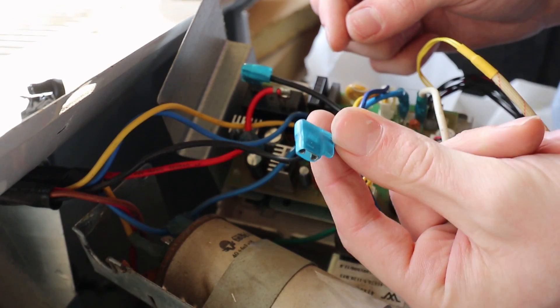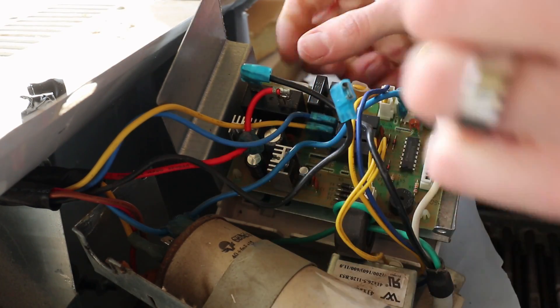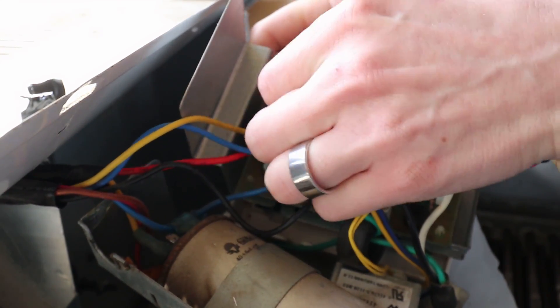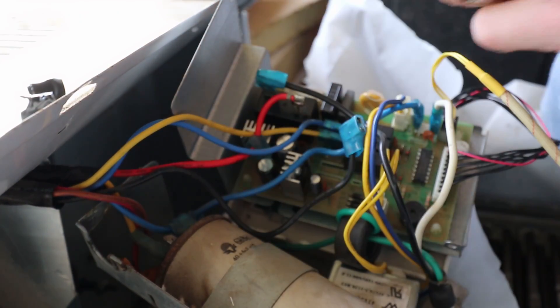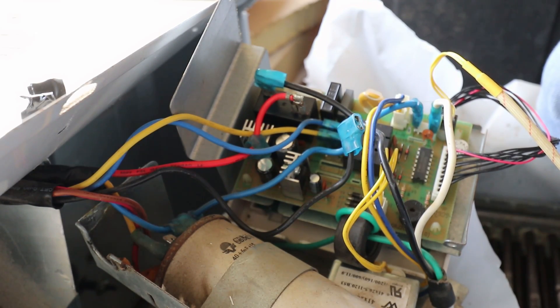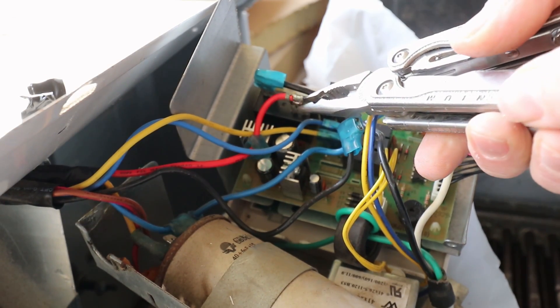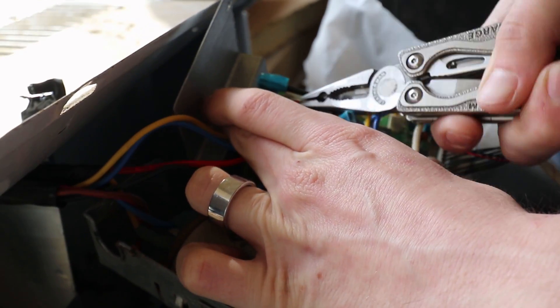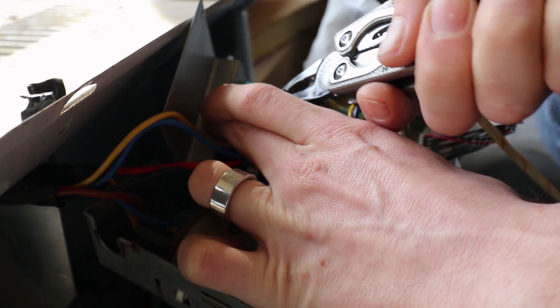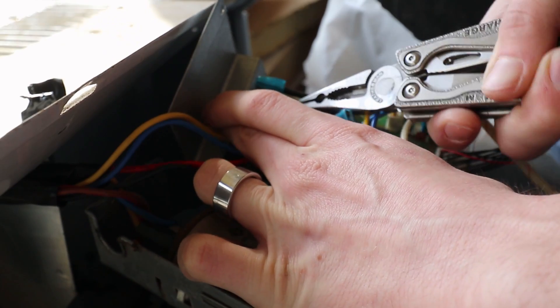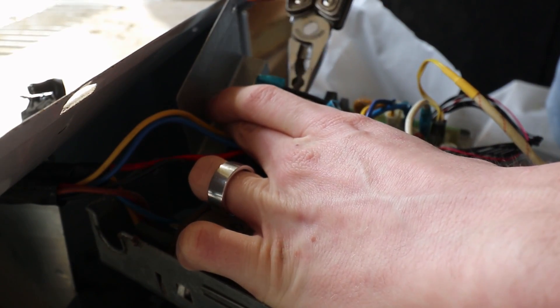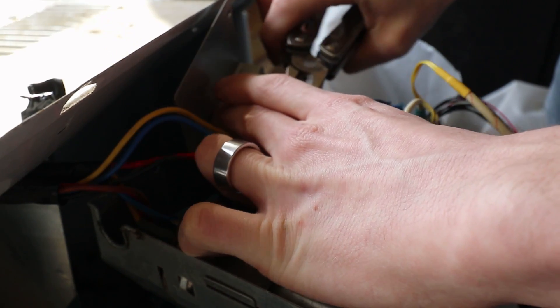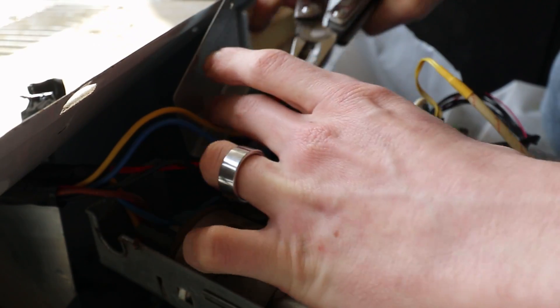So we've got what needs to be hot for our fan. We've got here what needs to be hot for our compressor. Keep in mind too that these capacitors can hold charge by design. They hold charge even when everything's unplugged, so be careful when you're in here messing around that you don't shock yourself.